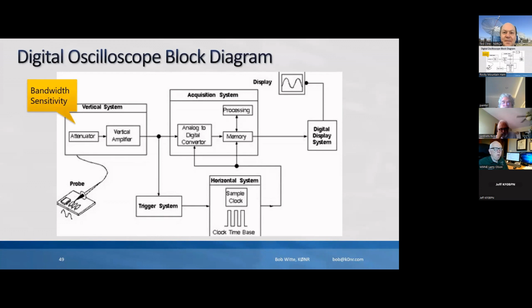So up front, the bandwidth of the scope is going to generally be limited by whatever amplifier circuitry you have up there, and the sensitivity. Usually these scopes go down to about 1 millivolt per division, that sort of thing. Then inside the acquisition system, the main issues are sample rate and resolution. Sample rate used to be a big deal because it was so expensive. The difference between a 20 megasample per second A to D and a gigasample A to D was so huge that when we were designing scopes, it was like, I'm just going to put as much sample rate as I can afford into that particular product. And it was always a limiting factor.